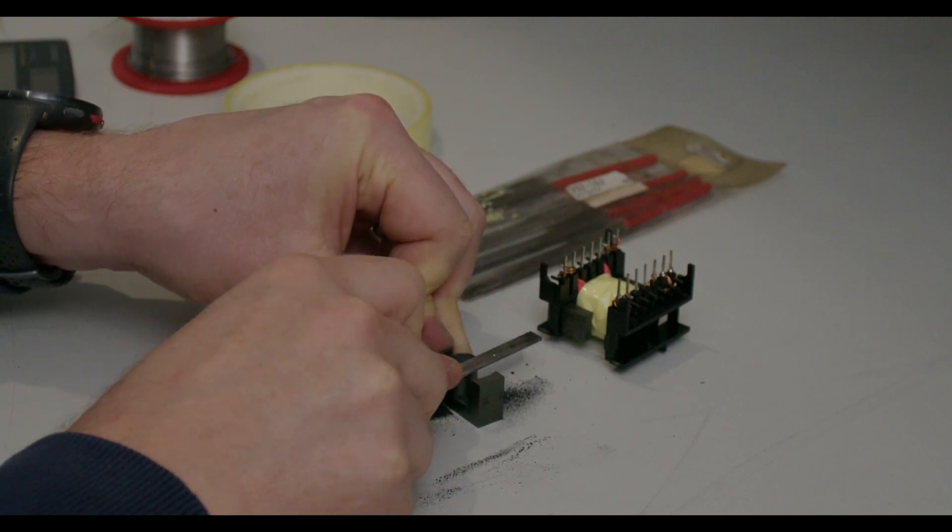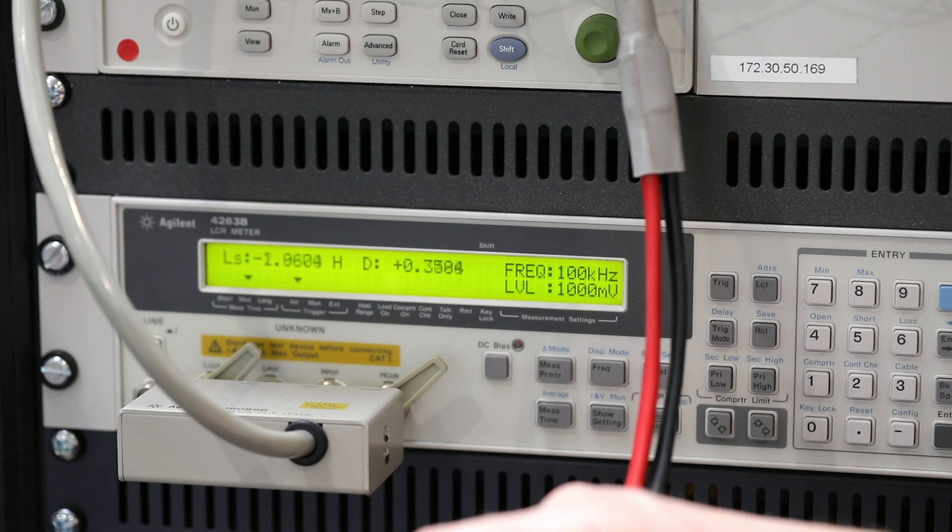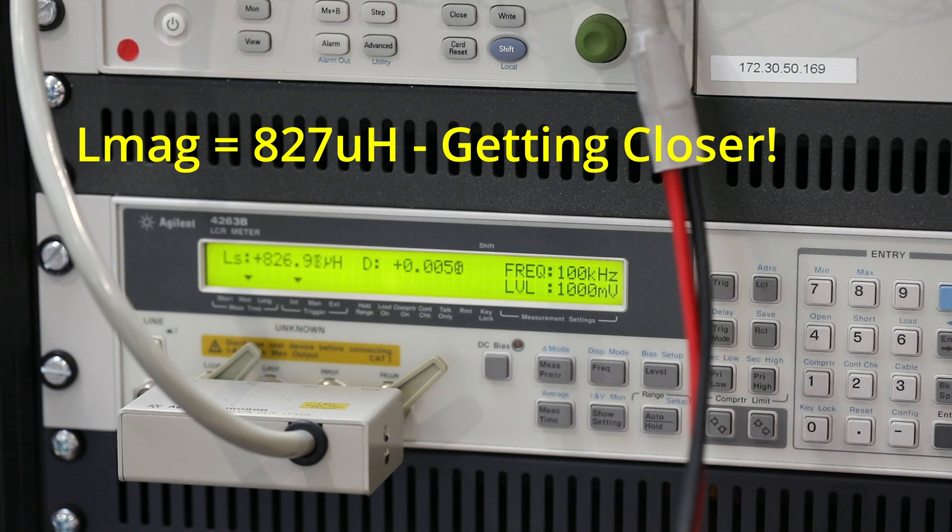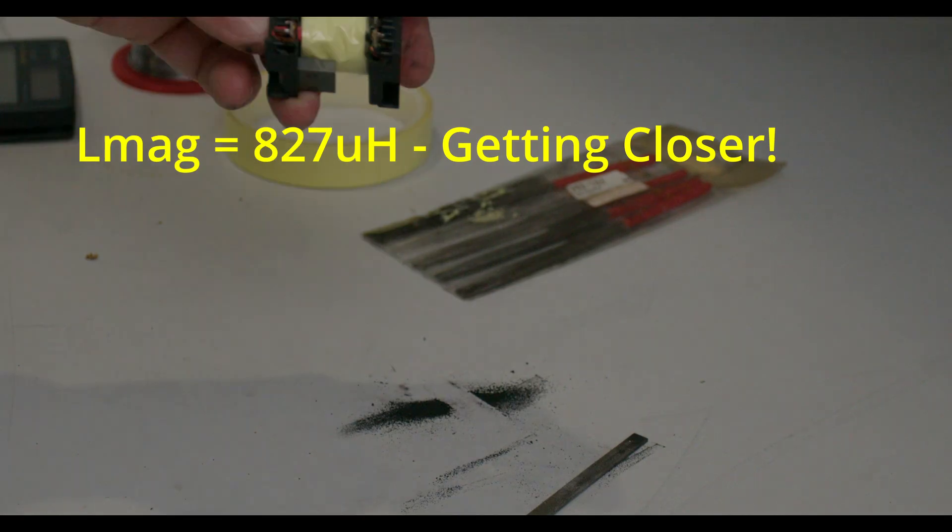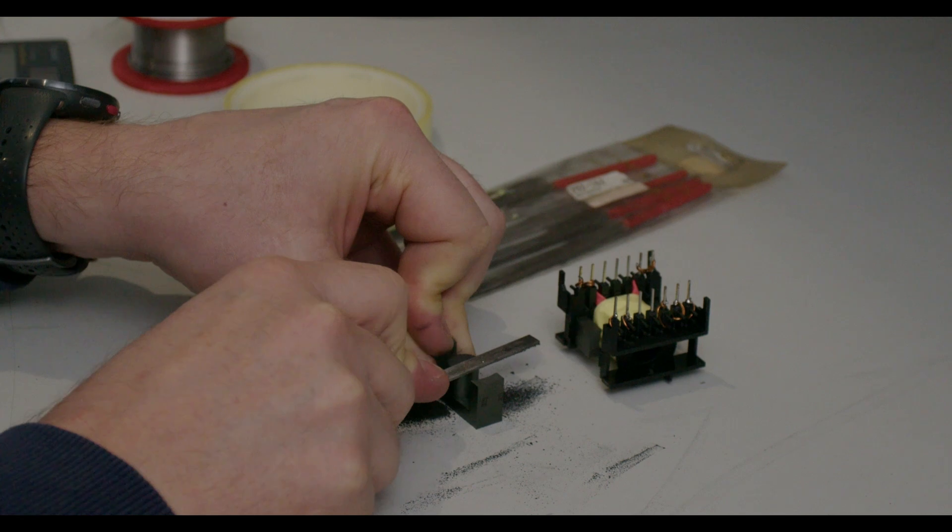We actually need to set the gap to give the required primary magnetising inductance of 700 microhenries with a tolerance of plus and minus 10%. Our calculations indicate this should be around 0.24mm, so we remove ferrite material a little at a time and measure using the impedance bridge to see if we are close enough.